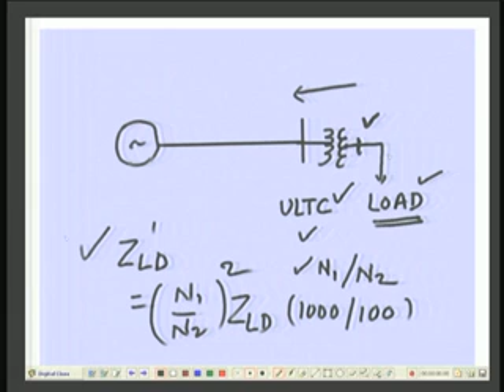But the moment you have provided ULTC which is trying to boost the voltage at the load point, you will find in a sequence that ULTC tries to increase the voltage, the impedance further decreases and so on. Is it understood like that? Therefore, the under load tap changer operation plays a very significant role in the stability of the power system.